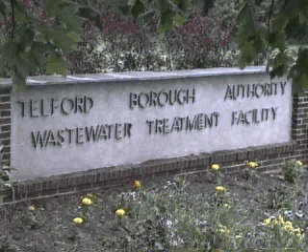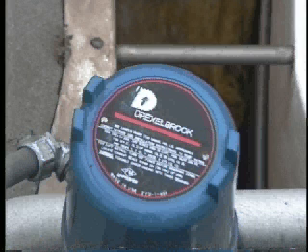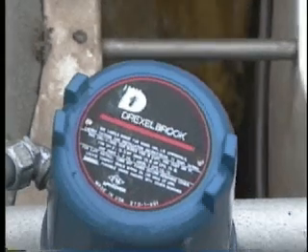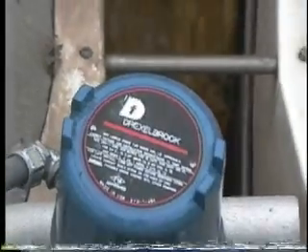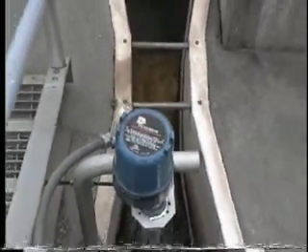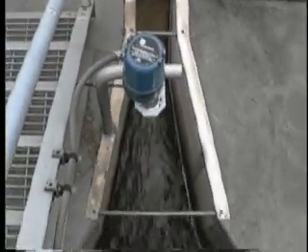Product spotlight on the Precision Digital PD 655 totalizer. We use the PD 655 as a transmitter — it works great with the Drexelbrook level sensor. We measure effluent flow in an open channel. The PD 655 converts the level measurement into gallons per hour. With the transmitter near the Drexelbrook, you don't pick up electrical noise.